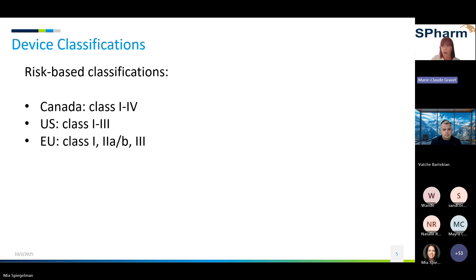their device. By comparison, the United States uses a three-class system, where the Class 3 englobe Canadian Class 3 and all of Class 4 devices. In Europe, they have also three-class category, where the Class 2B equivalent to Health Canada Class 3 devices. These differences pose challenges for global clinical development, requiring sponsors to reconcile classification and regulatory expectation across jurisdictions. Additionally, some products classified as medical devices in Europe may be considered as natural product in Canada based on our regulations, which can pose an additional set of challenges, including the GMP requirement for those type of products. Next slide, please.